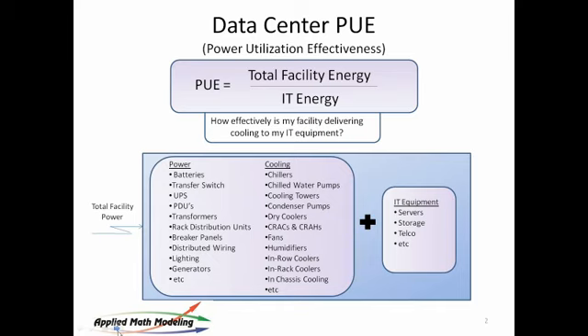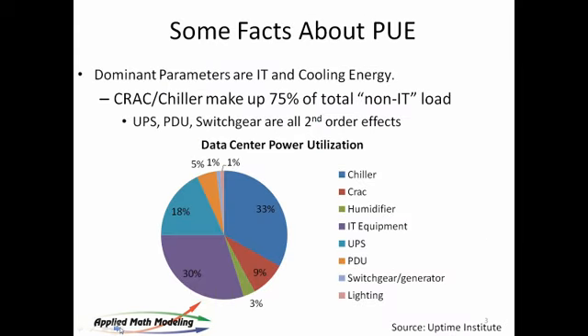But when you look at that big long list of things, you find that the dominant characteristics are really the cooling system. The cooling system itself makes up 75% of the non-IT load in the room. So things like inefficiencies in UPSs and PDUs are all second order. The primary thing is the CRAC and the chiller, the heat pump. It's getting the heat out of the room that is the dominant characteristic with respect to energy.